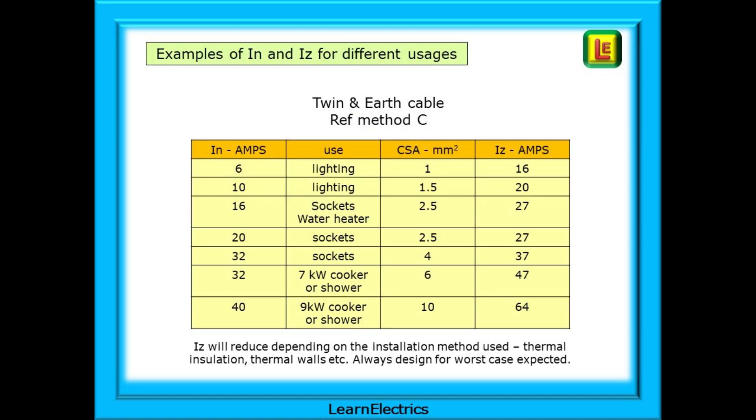This table shows some examples of IN and IZ for different usages. It is by no means a complete list, just an example to help with the video. This table is based on reference method C, or clipped direct, the simplest of the different installation conditions. As we start to pass the cable under loft insulation, through thermal walls, running it in trunking, etc., the rating of the conductors will reduce. The current carrying capacity of the cable will be reduced, and we may have to consider a larger CSA to cater for the same current. The appliance load will stay the same. It is the maximum current that we can put through the conductors that has reduced.